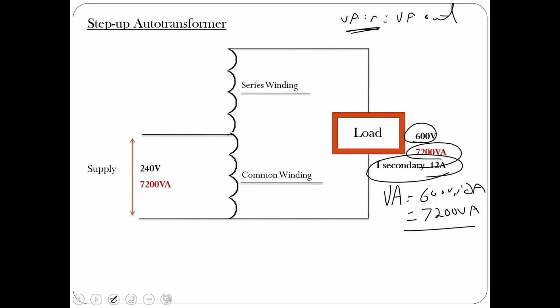And I can then use my voltage to calculate the I of the primary. We've already got the I of the secondary. It's 12 amps. So the I of the primary, we'd take 7200 and divide it by 240 volts. And that comes to 30 amps. So we've got 30 amps coming in right here. And whatever comes in has to go back, 30 amps.